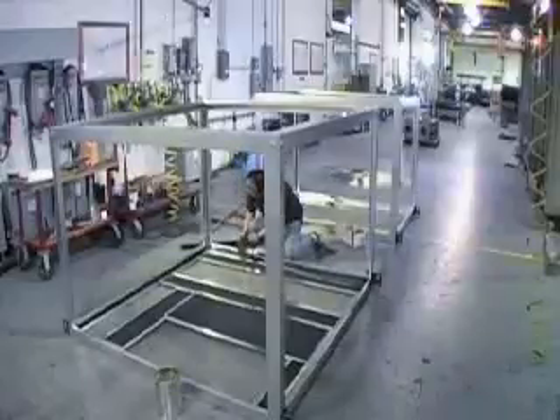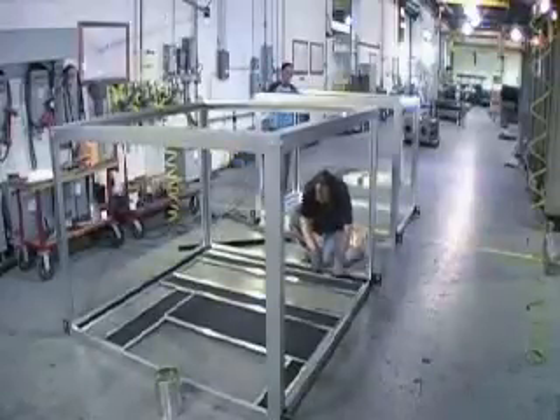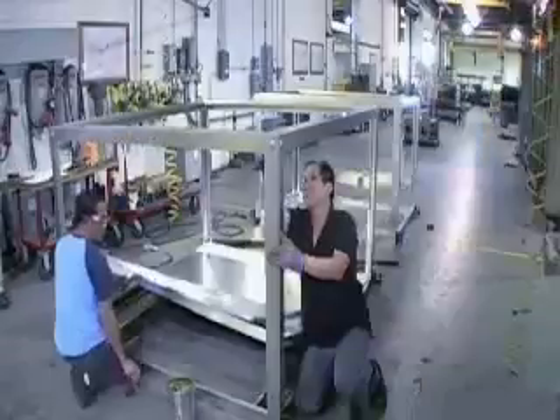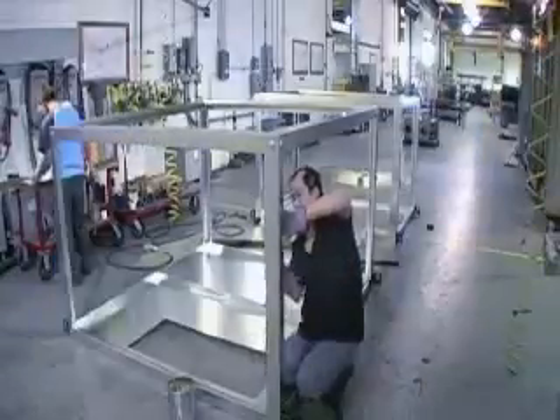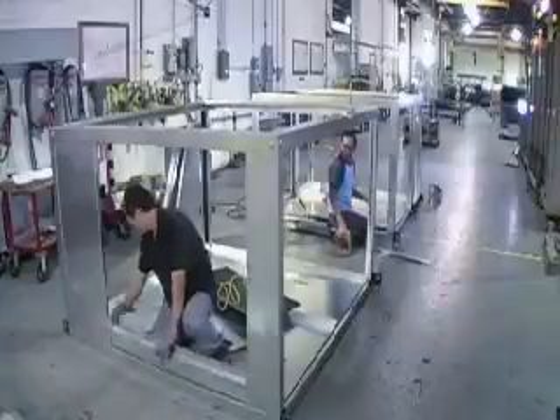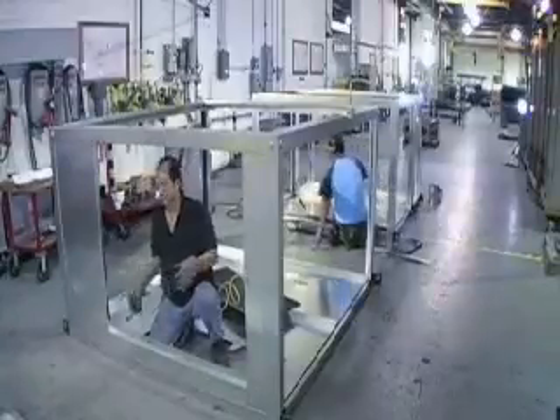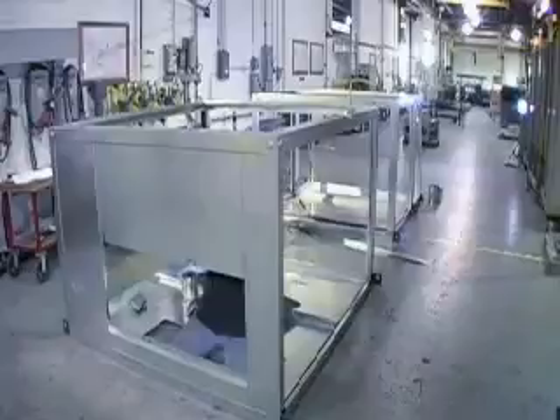I really think that the casing should be made with a double wall with insulation between it. Anything downstream of the cooling coil where condensation is likely to occur shouldn't have materials that absorb moisture. You come from the outside into the unit through some storm-proof louvers so you don't pull in snow and rain. Then we have a damper, and this is a two-position damper. It's not a control damper. It's either open or closed. But when it closes, we want it to be 100% closed. So we put in a 100% shut-off damper.